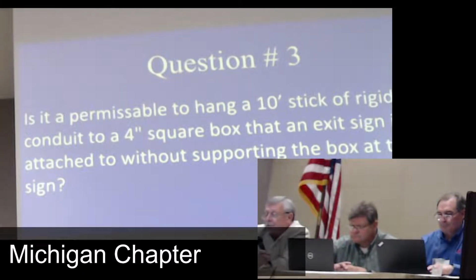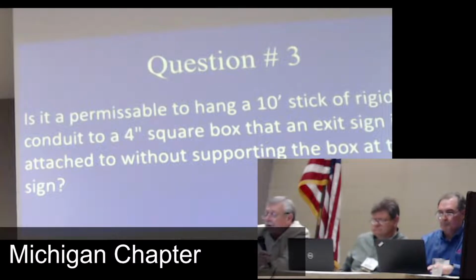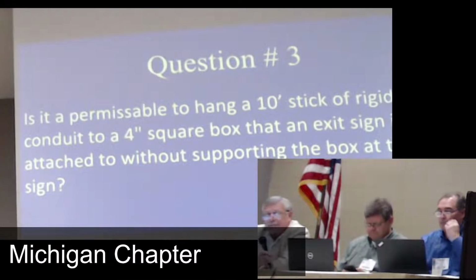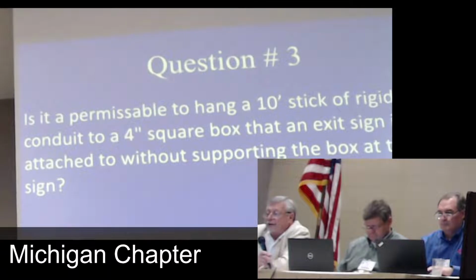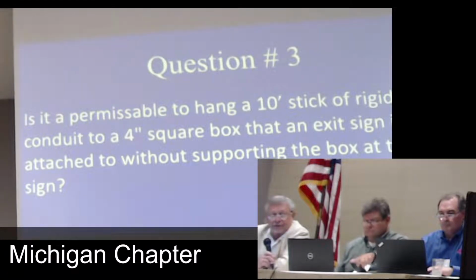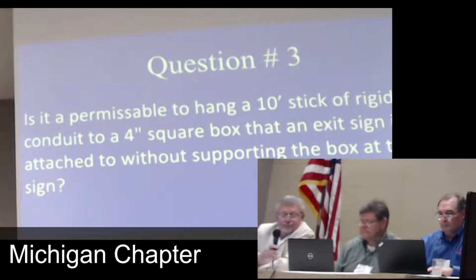There is an exception, number 2. It gives a little bit of relief from this, but there's a lot of conditions that I don't believe would be met here, primarily that this conduit must be secured within 36 inches of the enclosure. But with a bunch of conditions being met, you would have to take a look at it. Exception 2 could apply, but you really need to have threaded hubs, threaded enclosures going into that box. So, but my answer is probably not. Without a little more information, I can't say 100%. All right, questions, comments?